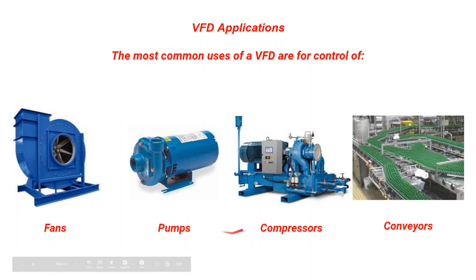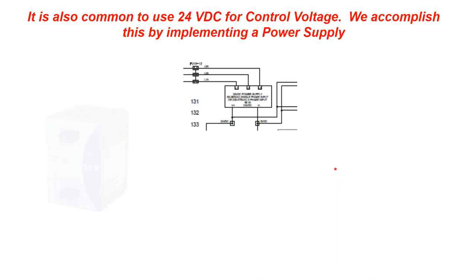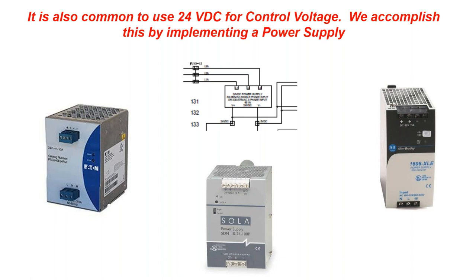For example, with a conveyor carrying bottles, starting abruptly could knock them over, as could stopping abruptly. A VFD allows you to ramp up and ramp down the conveyor speed smoothly. Moving on: the 120V section of the panel — derived from the transformer — powers things like receptacles or panel air conditioning units to keep the panel cool. We also have 24VDC control voltage, obtained using a power supply, which is what was used in the earlier video with the push button and light.